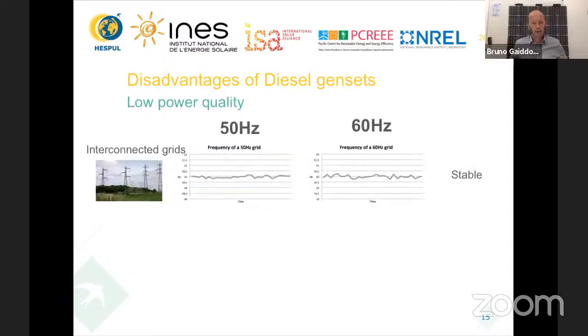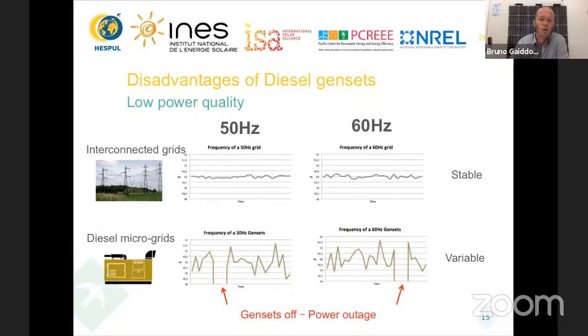Regarding power quality, the main indicator we can use to assess it is the frequency. Here's an example of the frequency of large interconnected grids on the mainland, which can be 50 hertz or 60 hertz. You see the frequency line stays close to the nominal value, but when you use a genset, you get much more fluctuation in the frequency.